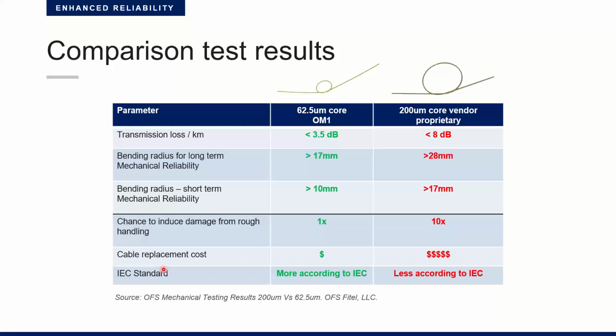Yeah, we heard during the last CIGRE session in Paris that some quite big utilities already specify installing fiber optic sensors to use them during the thermal heat run test during factory acceptance, in order to know really the hotspot factor, the winding gradient, and so on.